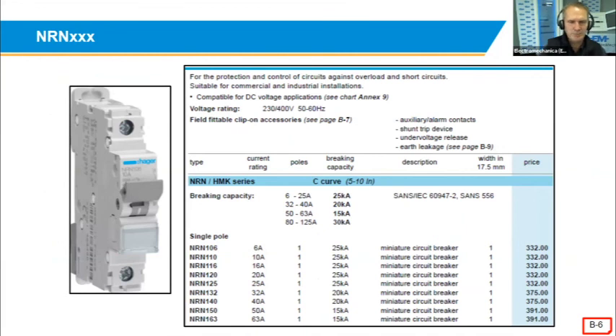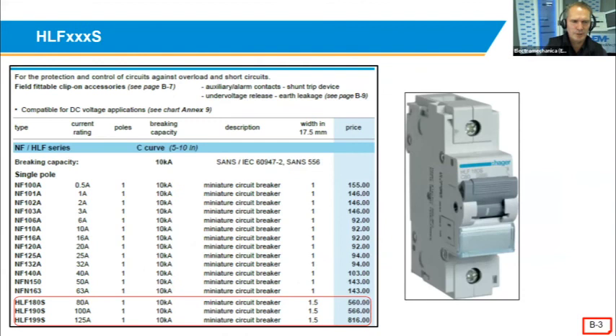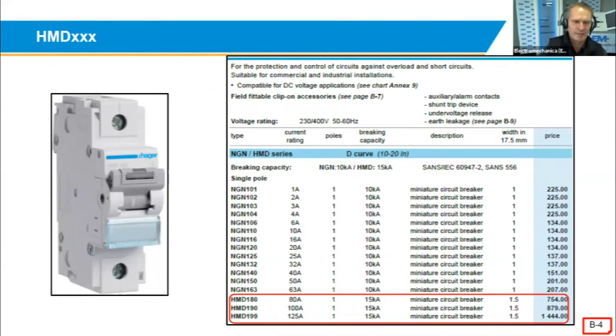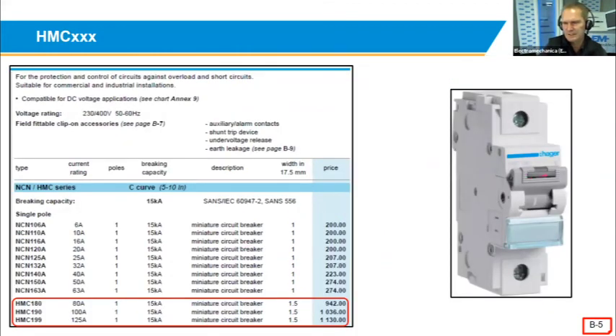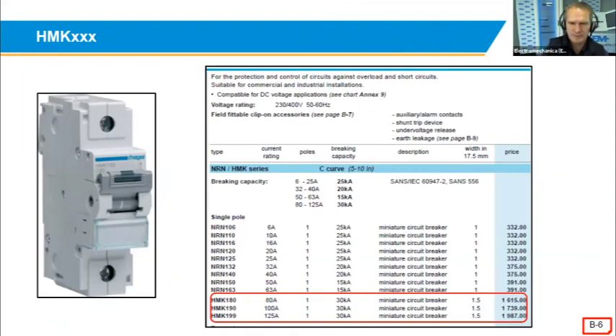So the NRN product, you'll see that it's got different fault levels depending on the current rating of it. So the NRN up to 63 amp can be used in a 15 kA application, and 6 to 25 amp, you can use it up to 25 kiloamps. Then if you go to the bigger products from 80 to 125 amps, the offer in there, you get a C curve, you'll find a D curve, and 15 kA again. And as mentioned again, you can see that there's the lockout possibility if you would like to use it on the breaker. 30 kA miniature circuit breaker.